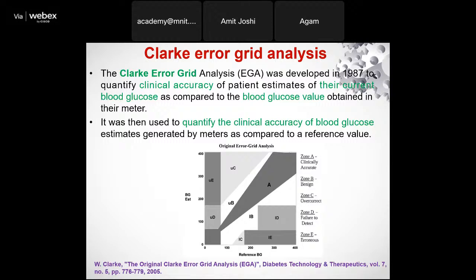Similarly, if the reading lies in zone B and C, then your device requires some correction, while D and E are erroneous performance where you simply need to throw away the device since it can no longer be used for clinical purposes.